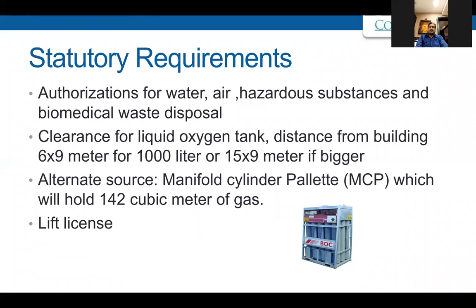Alternate source: nowadays companies are planning, because many of the old buildings, whatever they do, will not be able to get that 6 meter distance from the building for the liquid oxygen tank and that 9 meter height, because they are located in such a manner. So many of the companies have produced an innovative solution, called a manifold cylinder pallet, which has multiple cylinders built in a line arrangement, whereby one after another cylinder can be used through this machine.